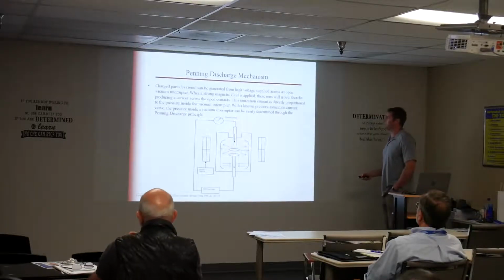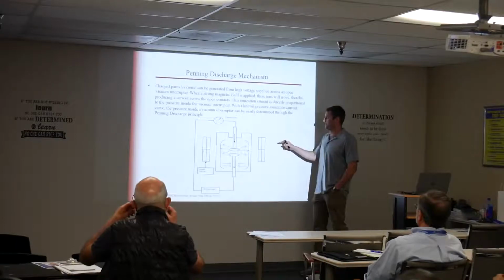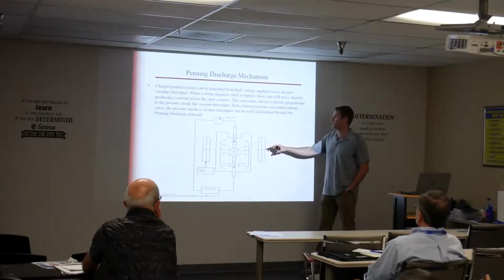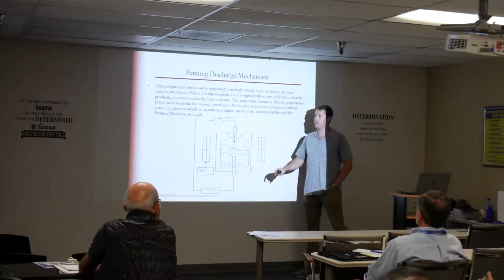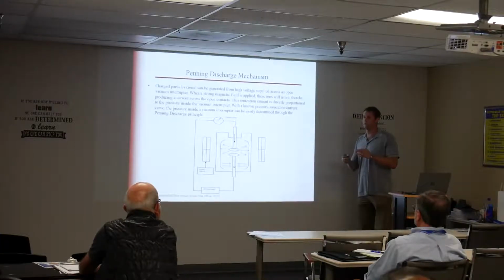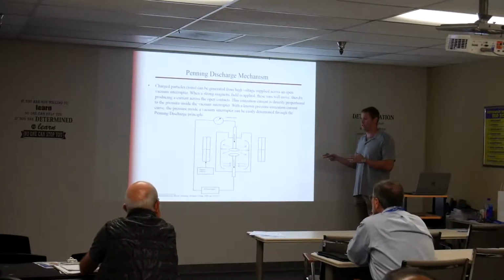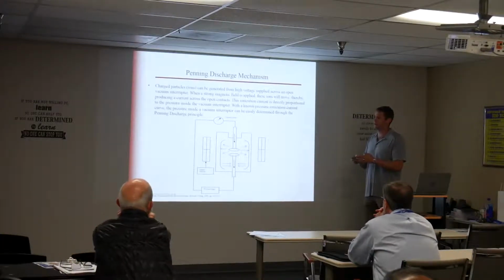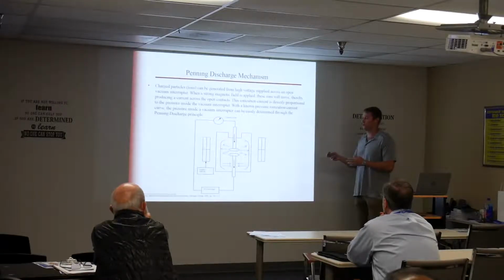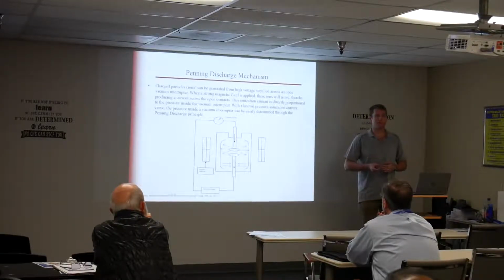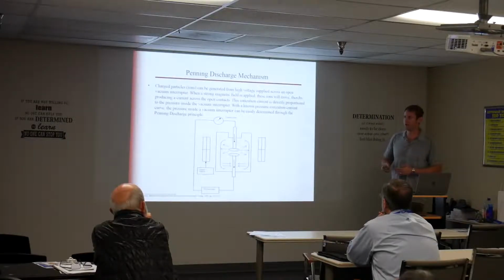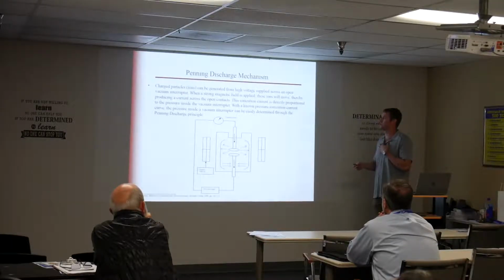But how we do that, so with our test, we're actually able to measure how much gas has leaked inside that interrupter and tell you the exact pressure or vacuum. We can tell you, okay, this is a brand new interrupter, you have 30 years. Okay, this interrupter is halfway through its life, you have 10 or 15 years, or this one might not make it to the next maintenance cycle. This is where you need to focus your attention on changing these interrupters out.